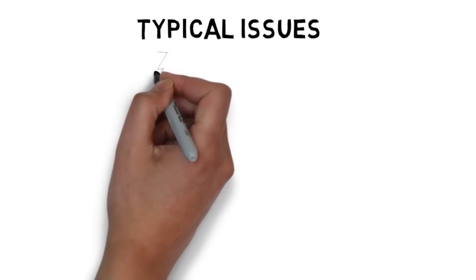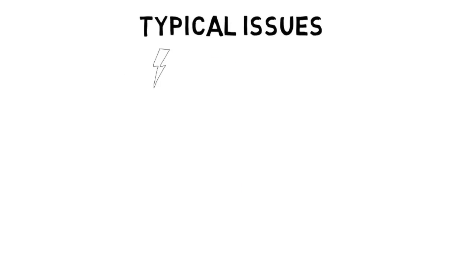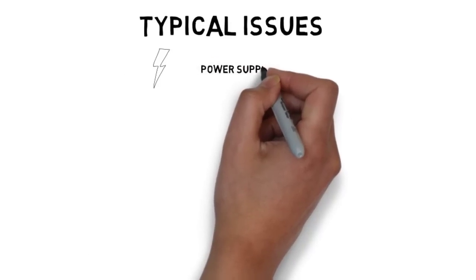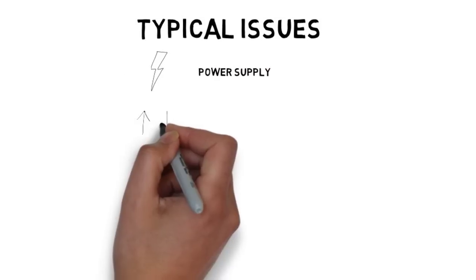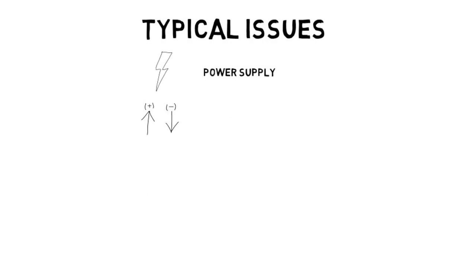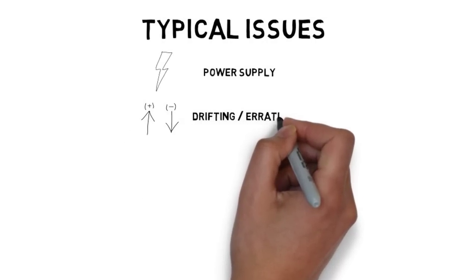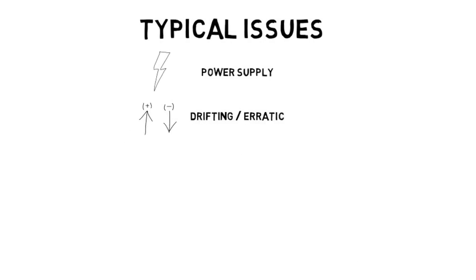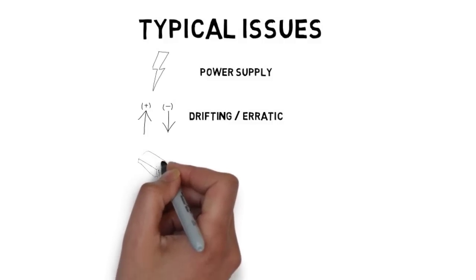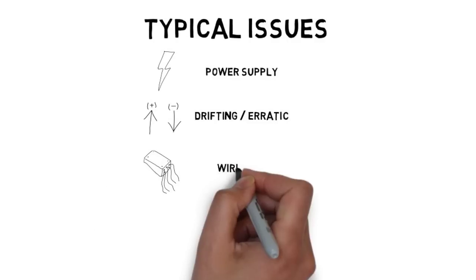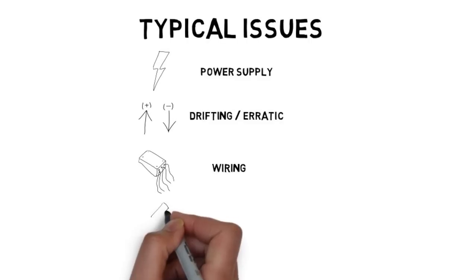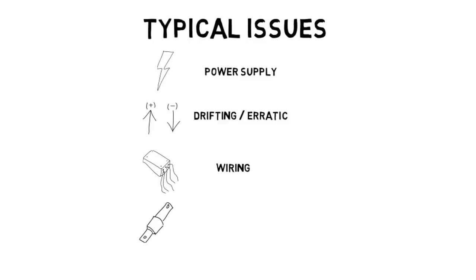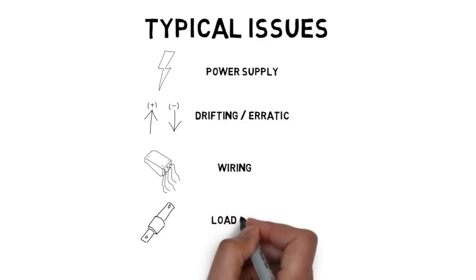These issues include power supply issues such as my indicator doesn't turn on, drifting or erratic weight issues, wiring issues such as a bad junction box, load cell cable or junction box cable, and finally a load cell issue which can cause drifting, erratic readings or inaccurate weights on your scale system.